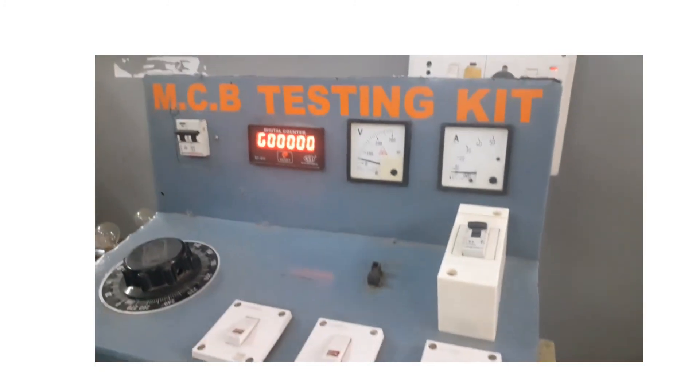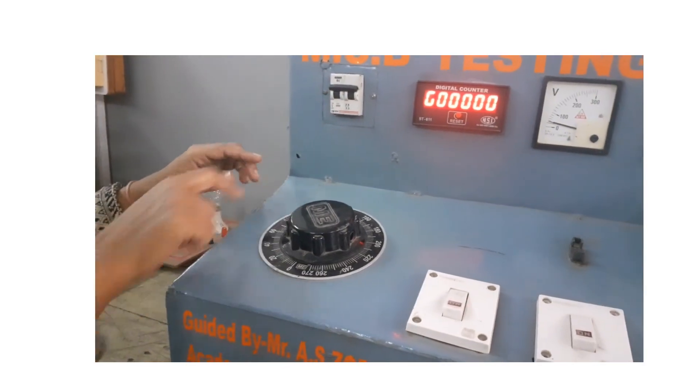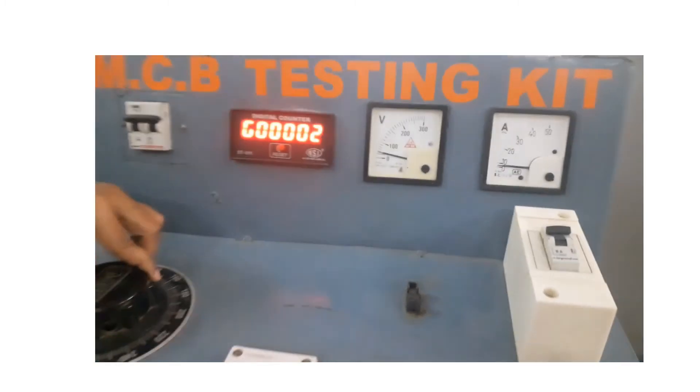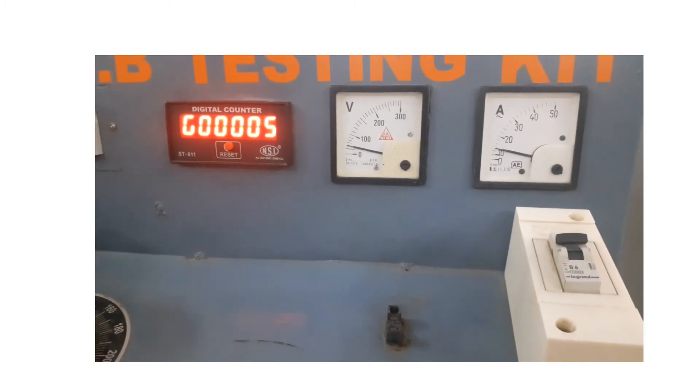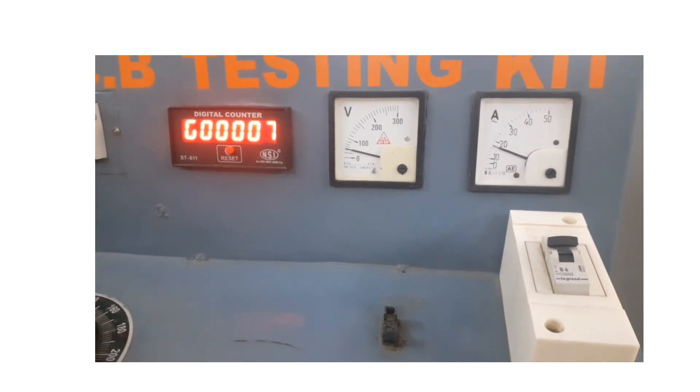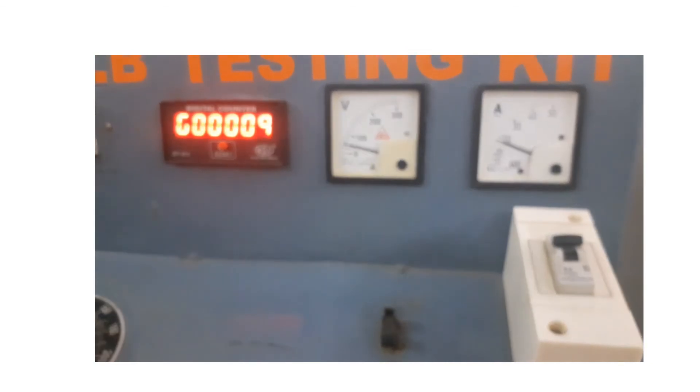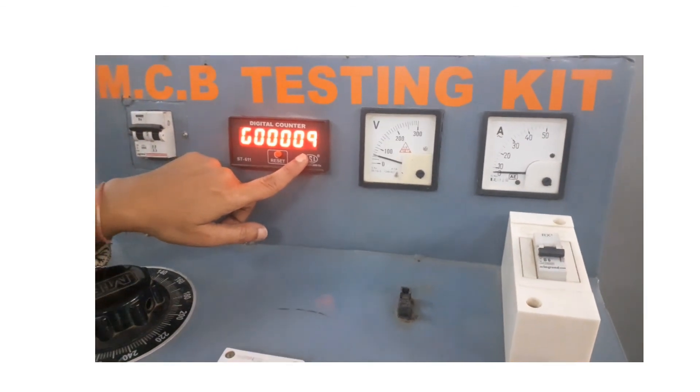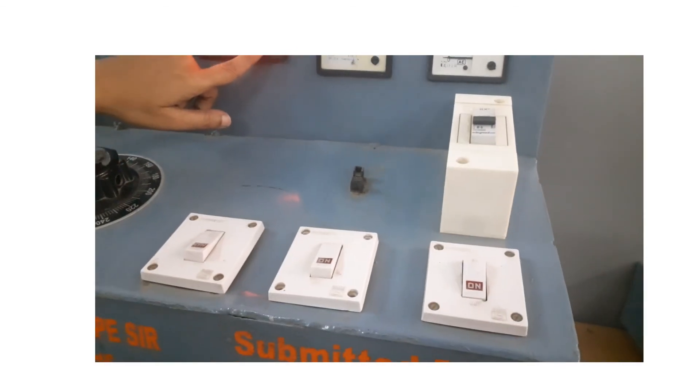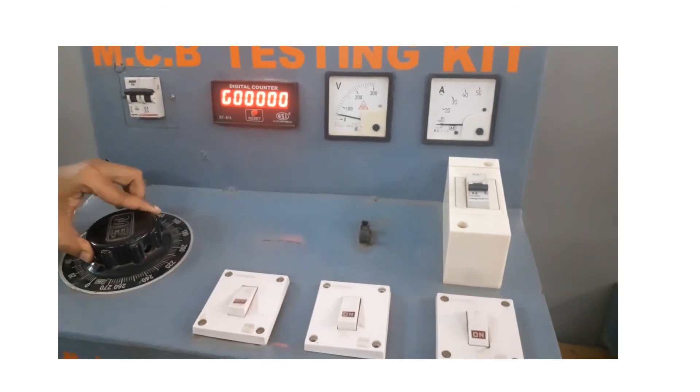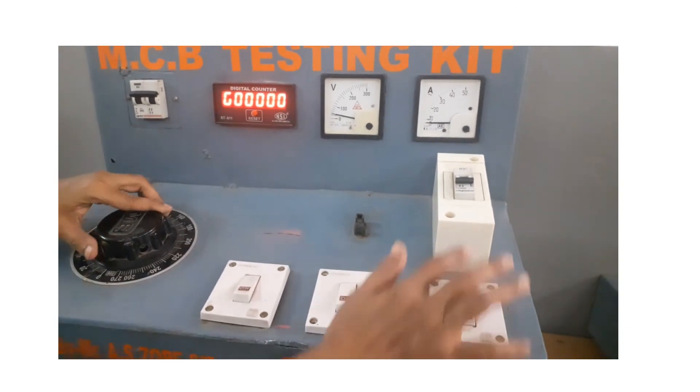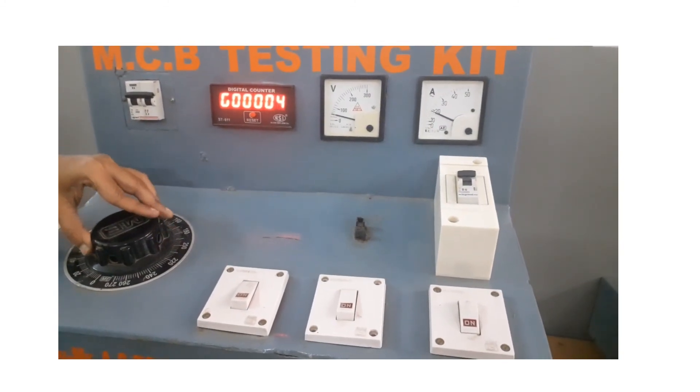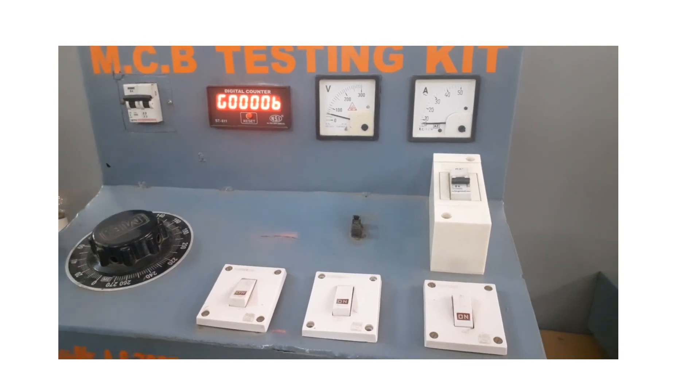I am going to set here 18 ampere current and when 18 ampere current flows through the system what happens just see. So second reading is whenever we are allowing 18 ampere current it is 3 times that of rated value 3 IN. So at that time it trips within 9 seconds.